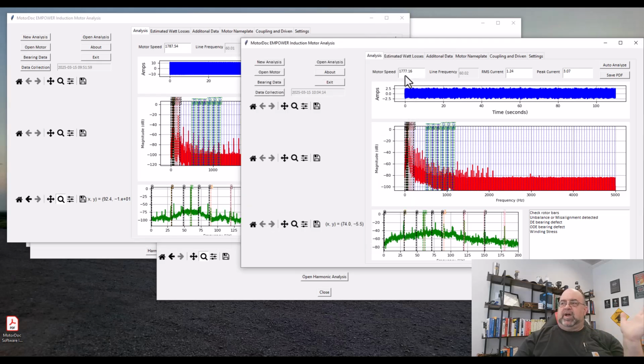1777, so it's off by about 10 RPM. Doesn't surprise me, because there may be something else doing that, or the raised noise floor may cause it. But here we go again. It's telling me I've got a DE bearing, ODE bearing, and winding stress issue, so I'm back to three false positives, three things that don't exist.